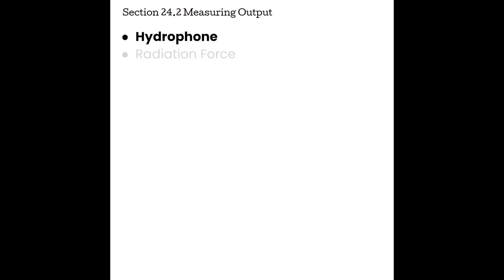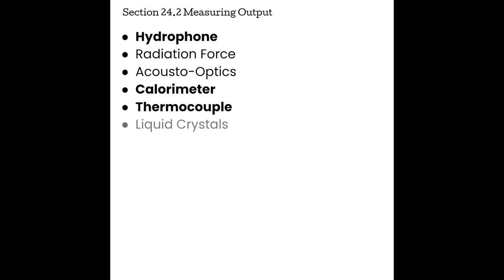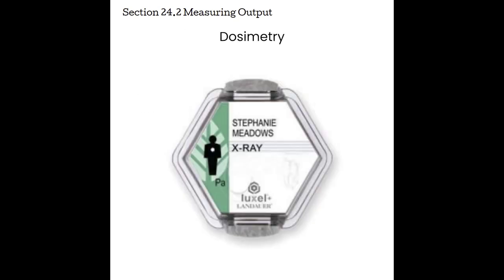There are multiple tools to do this with, such as the hydrophone, radiation force, acousto-optics, calorimeter, thermocouple, and liquid crystals. These tools can calculate the dose of ultrasound that a patient is getting. Dosimetry is the study of dosing, and it is typically used as the determination and measurement of the amount or dosage of radiation absorbed by a substance or living organism. As a side note, dosimeters are typically used to monitor personnel working with radioactive materials. Dosimeters are not typically worn by sonographers, but researchers do continue to evaluate the long-term bioeffects of ultrasound on patients and operators.